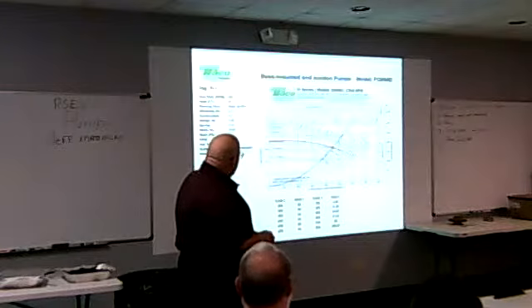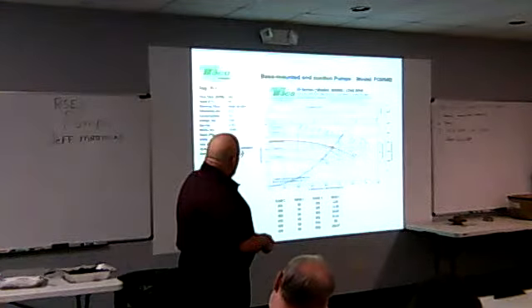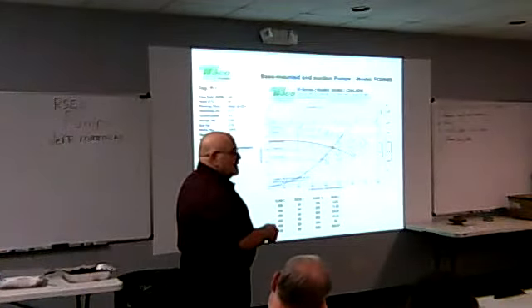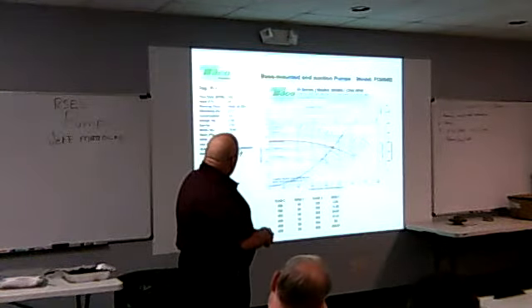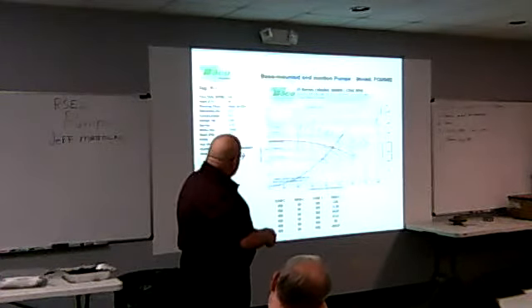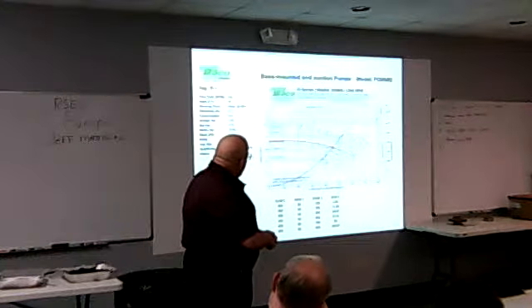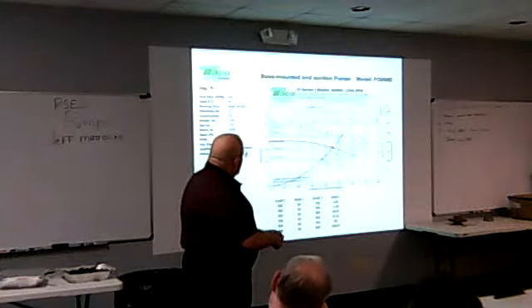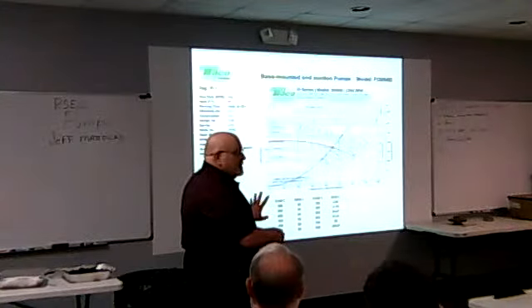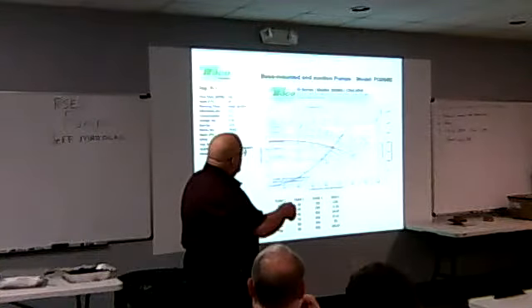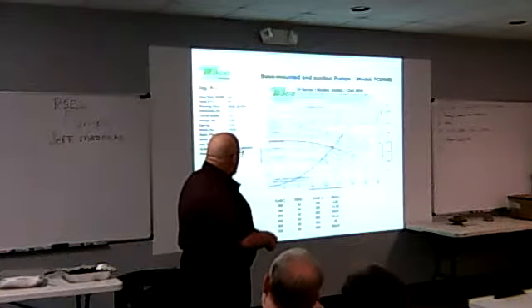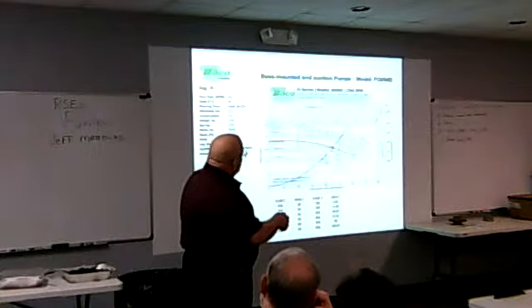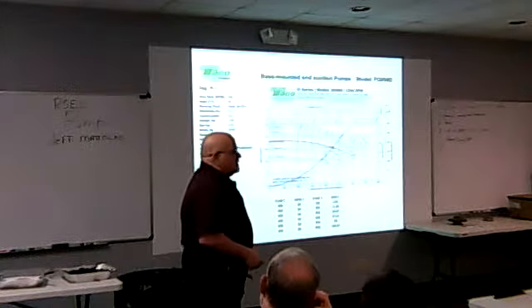Follow me? And I just went to this curve and said, okay, 100 GPM, I know I want 450 at 60. That's my duty point. I'll just pull 100 off here, put it in the equation, I get 2.96, I plot a point right there. Okay, let's go to 200. 11.85, I plot a point there. I use the same number, put in 326.67. It's all from that affinity curve with a square, okay? And that's why we have a hyperbolic curve, because it's varying as a square. I can just keep picking numbers and plotting this and draw this in. Now I have my system curve.